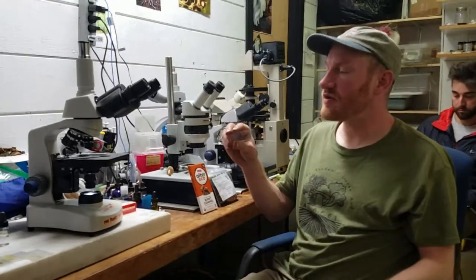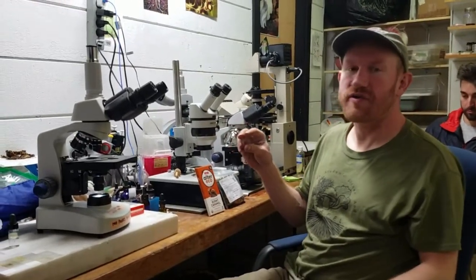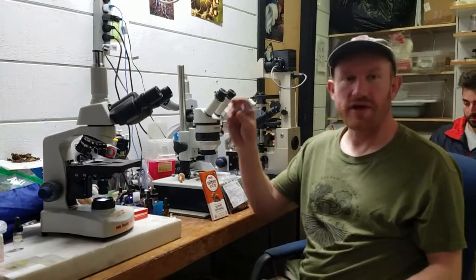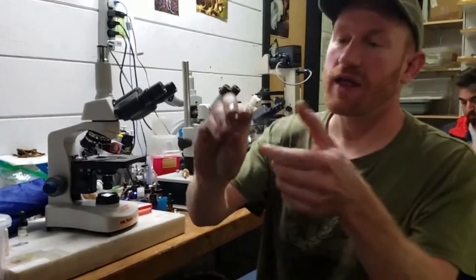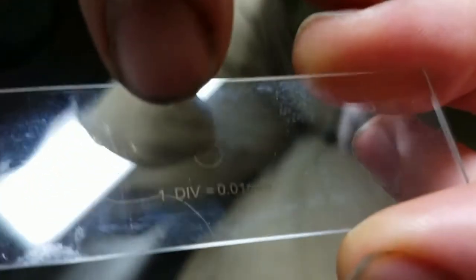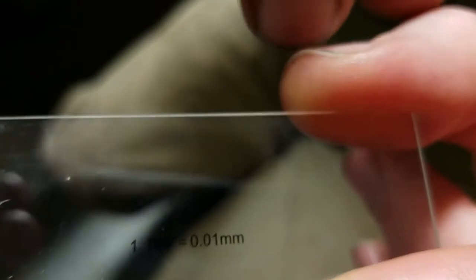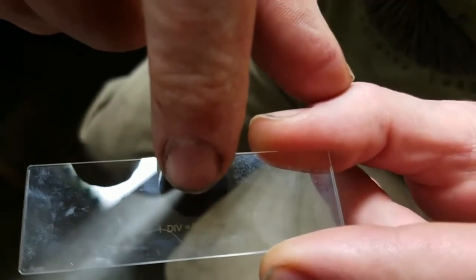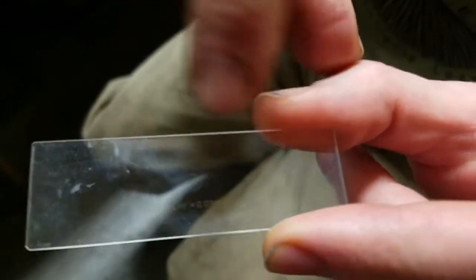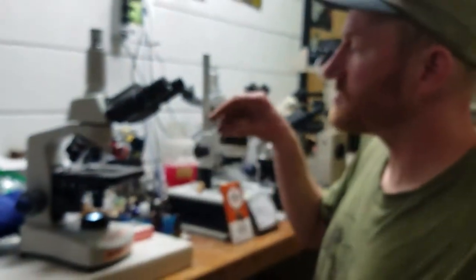So we're going to make a video on how to calibrate your microscope using a stage micrometer. So here's a stage micrometer, and it's just a regular microscope slide, except that it has some printing on it. And so this stage micrometer is just the $10 Amscope stage micrometer, and this one division is 0.01 millimeters, so that's 10 micrometers per division. So what we need to do is take a picture of the stage micrometer using the different objectives.